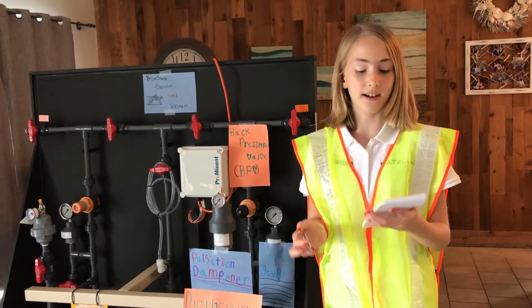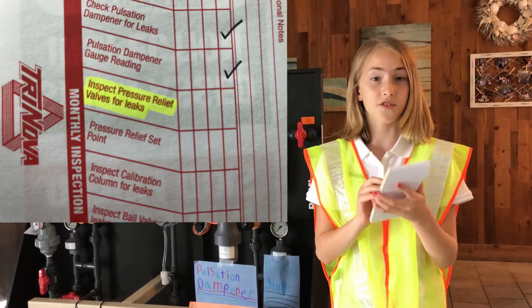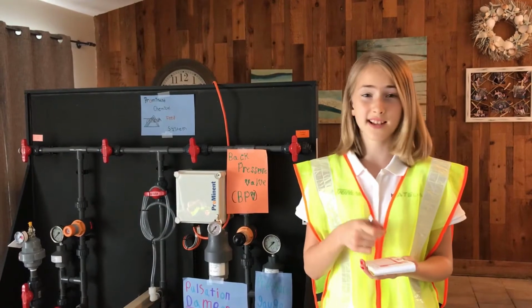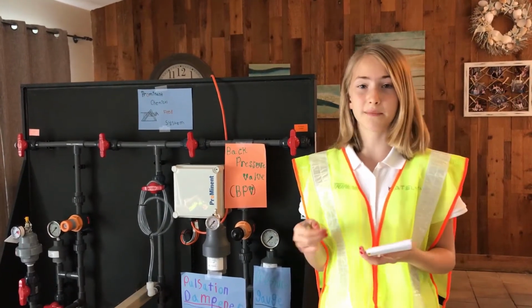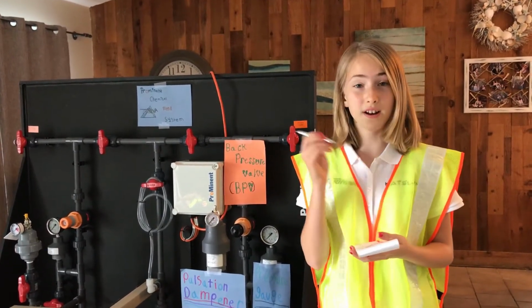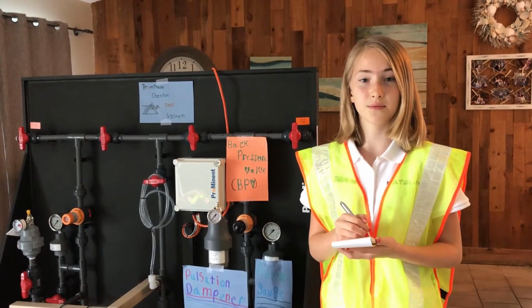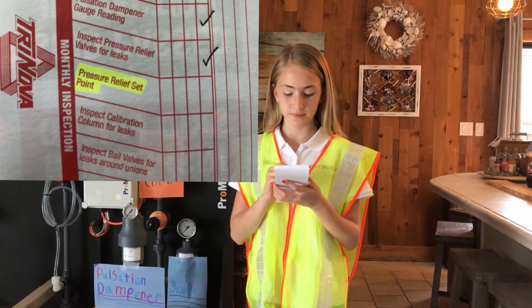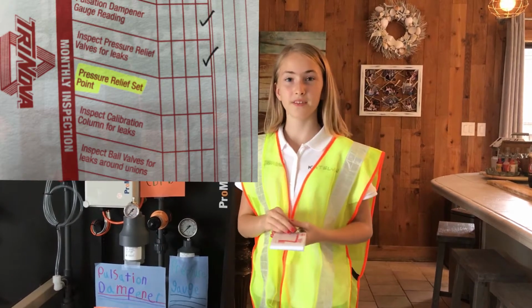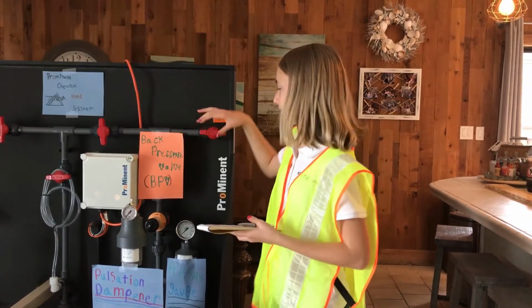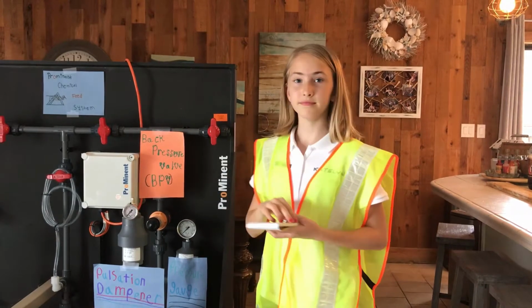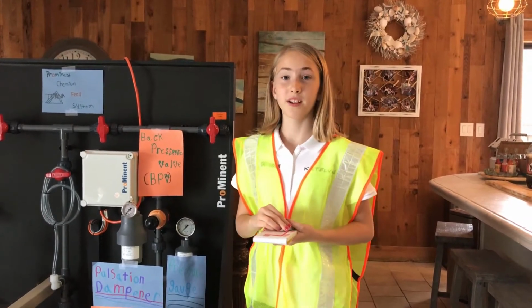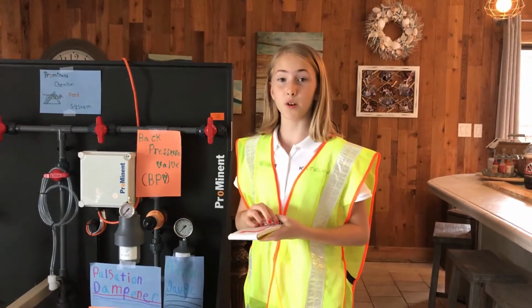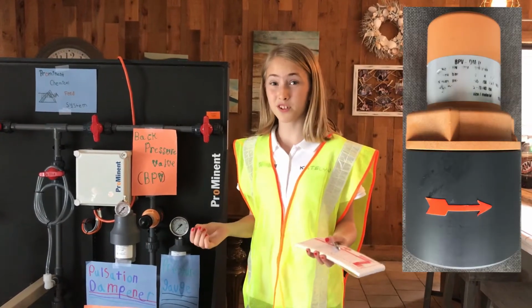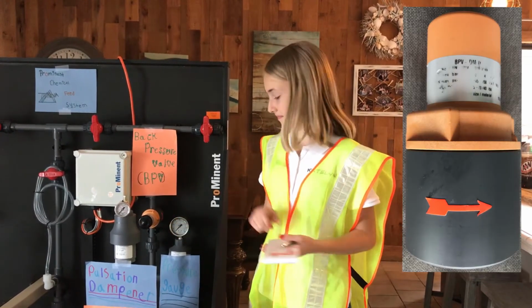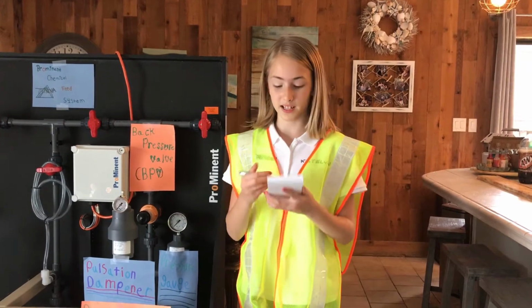Seventh thing we're going to look at is inspect pressure relief valves for leaks. That includes any crystallization, water, moisture, or dampness. Really check where there are those threaded areas and pay attention to those for leaks. Step 8 on the checklist, pressure relief set point. First, close the discharge valve. Watch the pressure gauge. Verify it climbs to the relief point. Does the relief valve open to release the built-up pressure? If it works properly, give it a check mark.